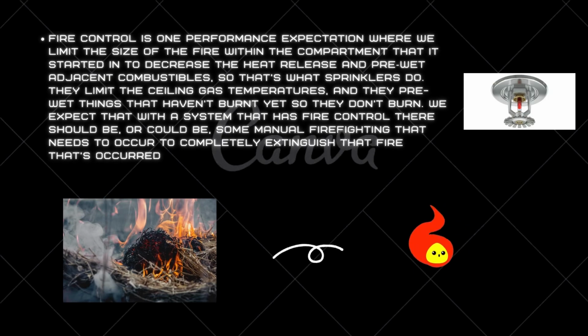Fire control is one performance expectation where we limit the size of the fire within the compartment that it started in to decrease the heat release and prevent adjacent combustibles from burning. So that is what sprinklers do. They limit the ceiling gas temperature and they prevent things that haven't burned yet from burning. We expect that with a system that has fire control, there should be or could be some manual firefighting that needs to occur to completely extinguish the fire.